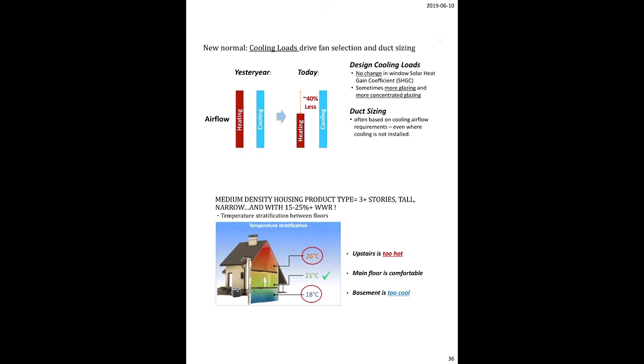The other thing that I want you to keep in mind is that low load homes, if you're principally using forced air systems, air source heat pumps, geo systems like that, you have to remember that you're actually moving, in some cases, air at a lower velocity. You might be using higher volumes over time, but you're actually losing velocity. And what we're finding is we're starting to get homes that have lots of stagnant zones in them, so areas where the air is not mixing. Traditional duct systems are designed on what's called displacement. In other words, the air pushes into the room through a register and it displaces the air out where? Return air. And that's what it was designed as.